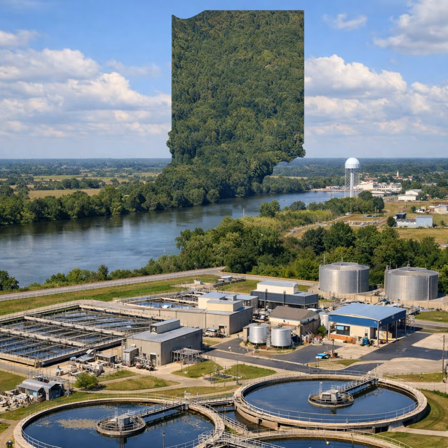But you don't want too many of them, because if you have too many filaments, it will cause sludge not to settle properly, causing sludge bulking. So the sludge will bulk and rise up in the tanks and the clarifiers, and you'll see that it's not compacting properly because there are too many filaments.